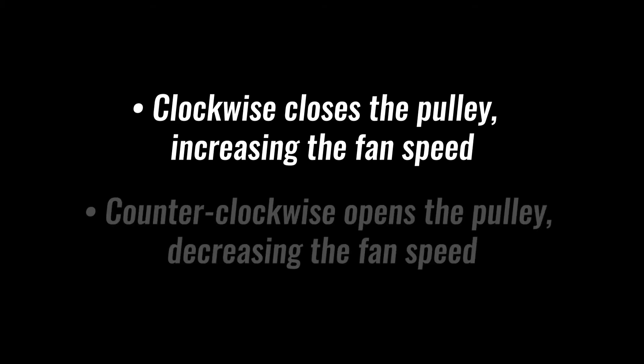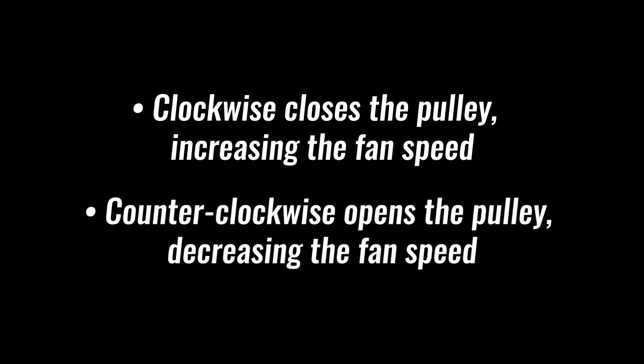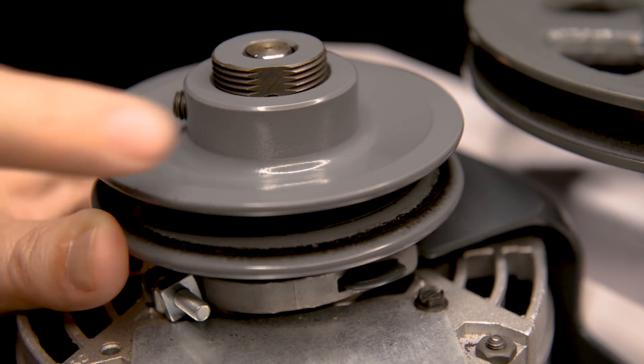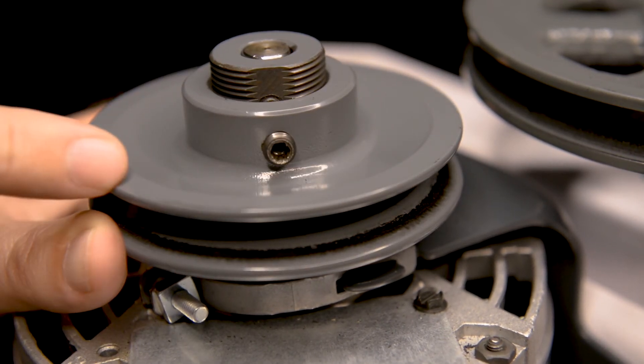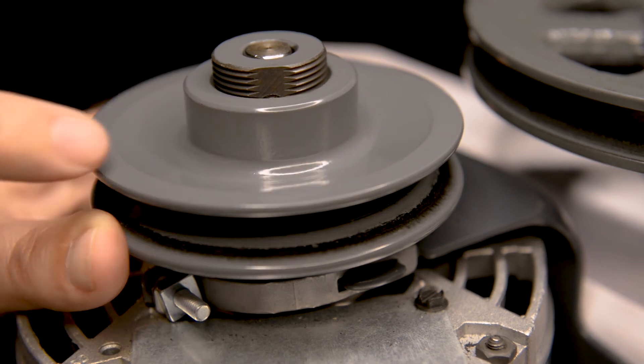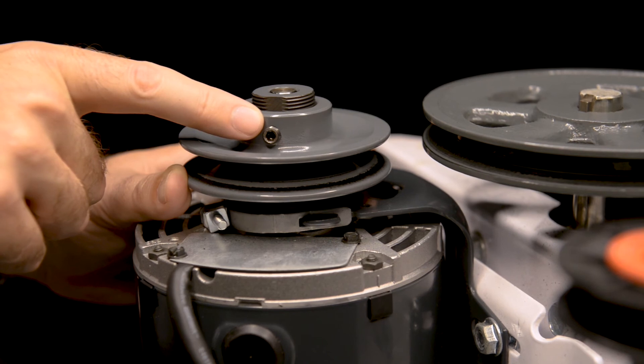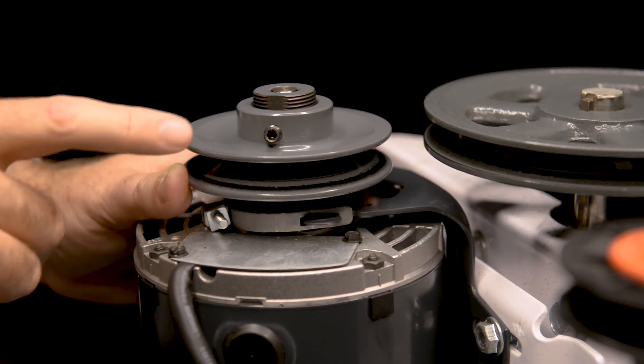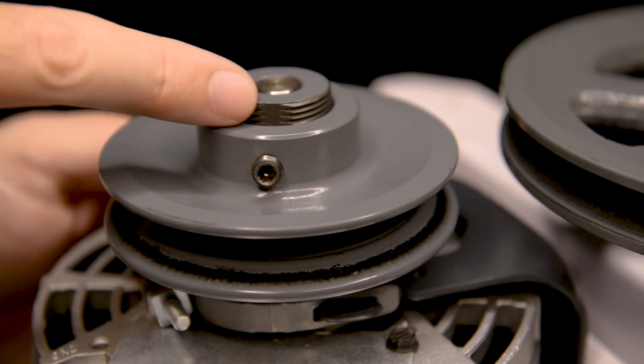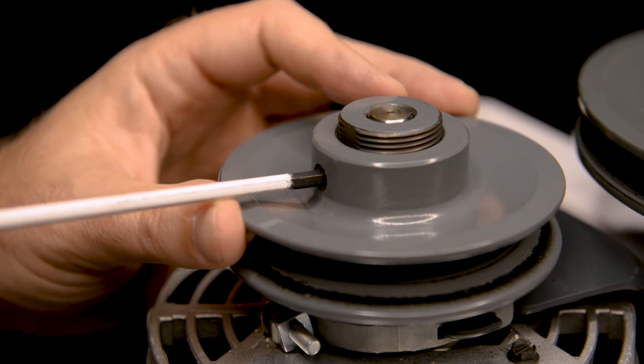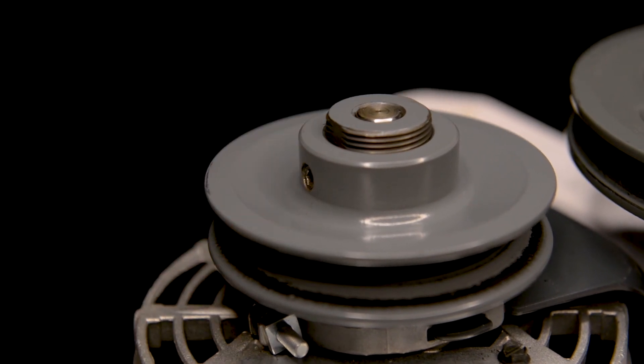Turning the pulley clockwise closes the pulley, increasing its effective diameter and increasing the fan speed. Turning the pulley counterclockwise opens the pulley, decreasing the effective diameter and decreasing the fan speed. When setting the pulley, always turn the pulley clockwise until it's fully closed. From that point, turn it counterclockwise the appropriate number of turns to attain the proper speed. This setting is commonly referred to as the number of turns open. Once the desired setting is achieved, make sure the set screw lines up with the flat spot where there are not threads to interfere with the set screw. Tighten the set screw per manufacturer's recommendations, which can be found in the fan's installation and operation manual.